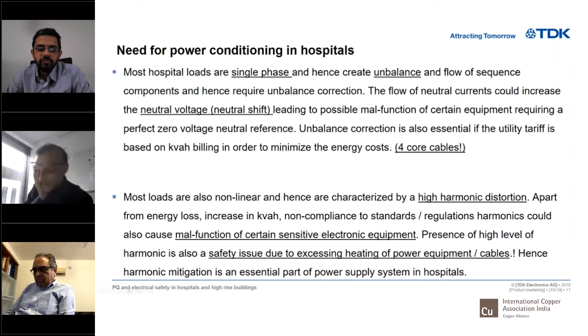The second one is most of them have a high harmonic distortion because all of them have switched mode power supplies. That means there's excessive heating, more currents, RMS currents go up. When the currents go up, you have excess power loss, not only because of higher RMS currents, but also because of skin and proximity effect. Then we have the low power factor issues, and most of the equipment in hospitals is sensitive electronic instrumentation, and they require near perfect sinusoidal excitation. So if the input power supply is corrupted, either because of the grid power supply not being good or because of you injecting harmonics through a source impedance, whatever be the reason, some of this equipment starts malfunctioning.